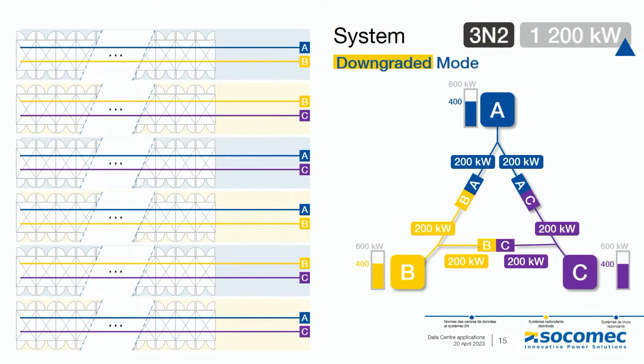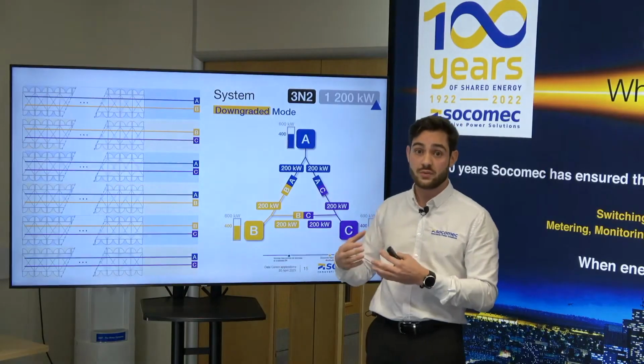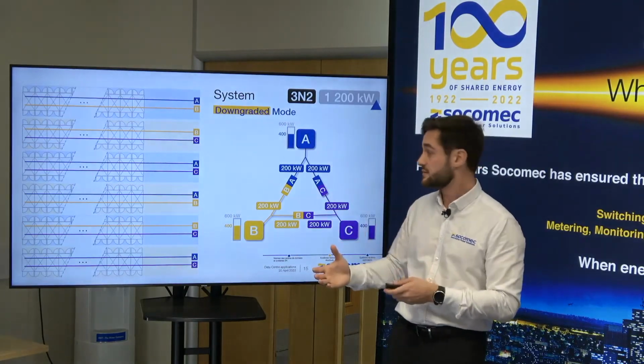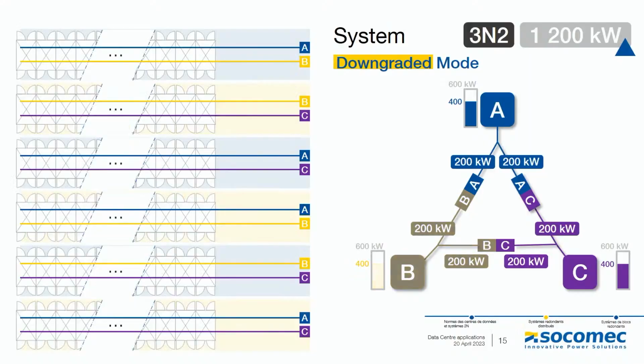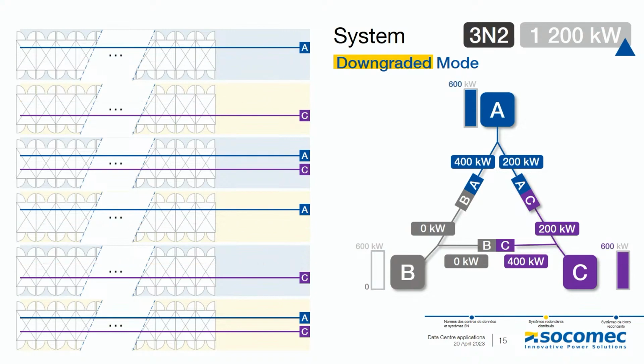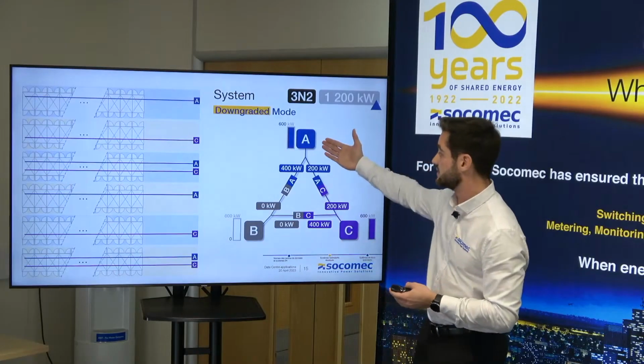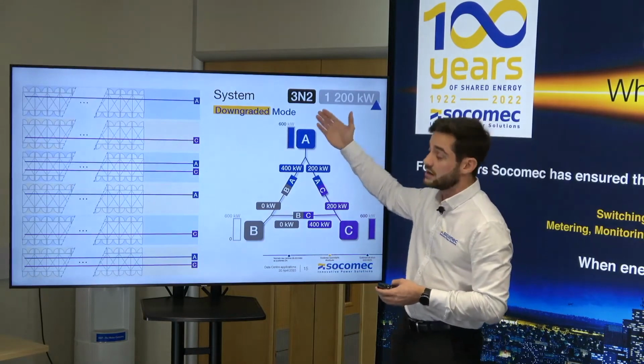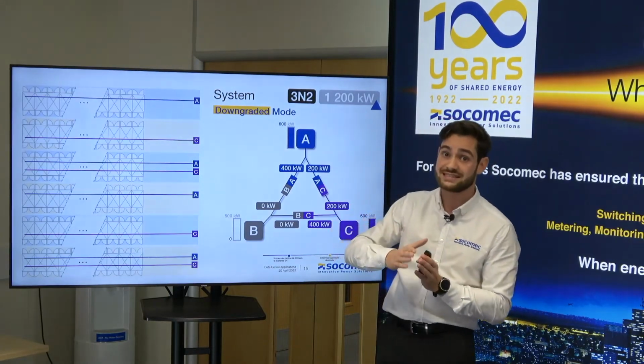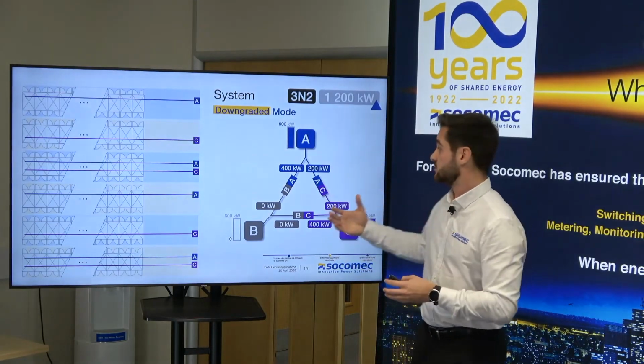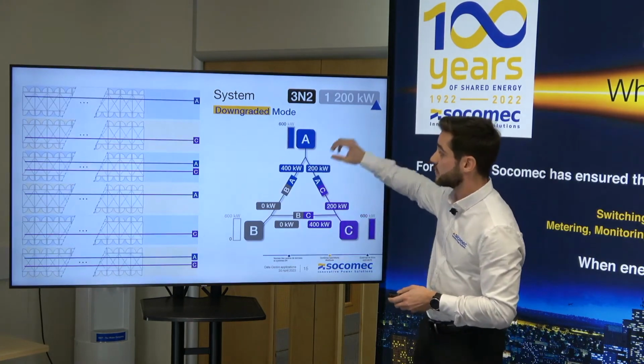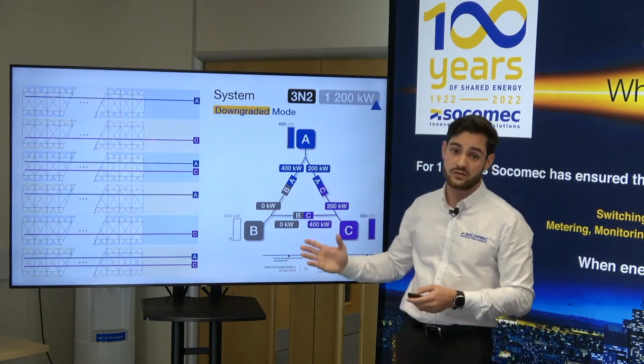Imagine, in normal mode, we are sharing the load across the 3 UPS systems. But now imagine you've got a failure, let's say on UPS system B. You have 400 kilowatts that was covered by this UPS system that needs to be covered by the 2 remaining systems, which is absolutely fine because they are sized for that. So you can see that they've kicked in and taken the load from 400 kilowatts each to 600 kilowatts. So we are still able, with 2 systems, to cover the overall load of 1200 kilowatts.